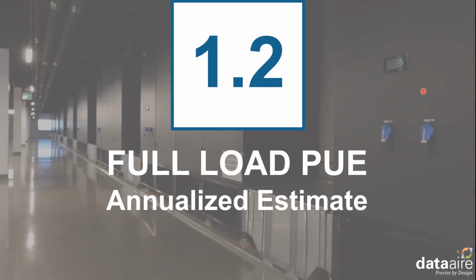So a PUE of 2.0 is horrible, but it's very common. A lot of data centers are operating at that level. More commonly, a good data center is going to operate at a PUE between 1.5 and 1.7. Those are very common numbers.